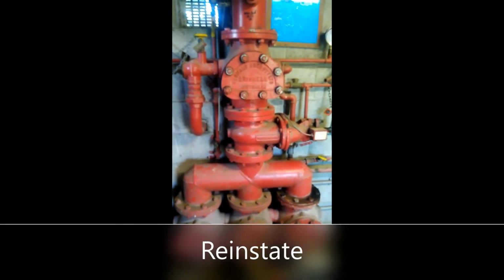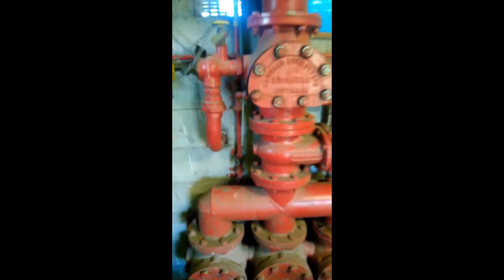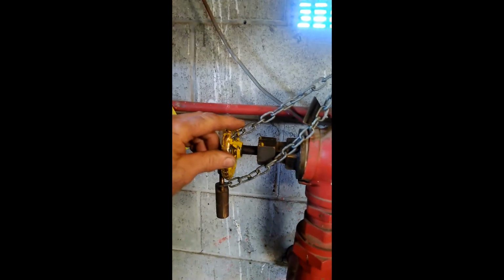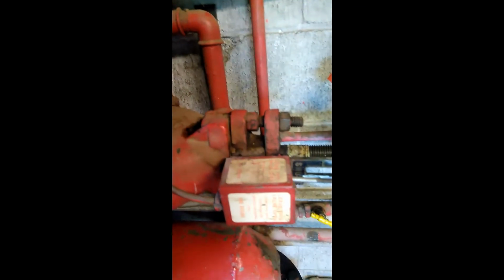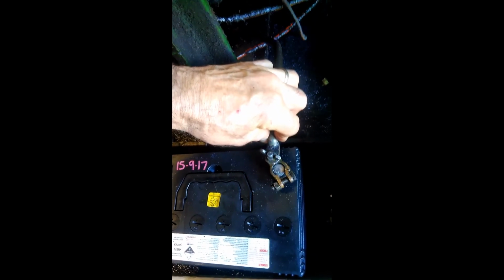To reinstate the sprinkler system at Kiwi Lumbar, first you've got to go across and shut the main drain. Then you open the main stop valve. Then you open one of the jockey pump lines and then open the other jockey pump line. Then you go across to your diesel and just touch one of the battery leads on, your diesel motor will start.